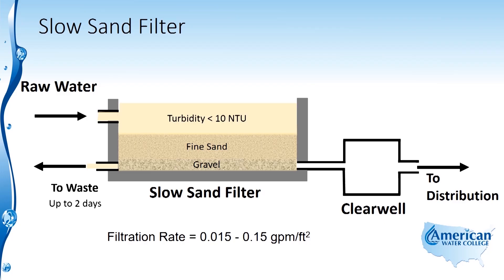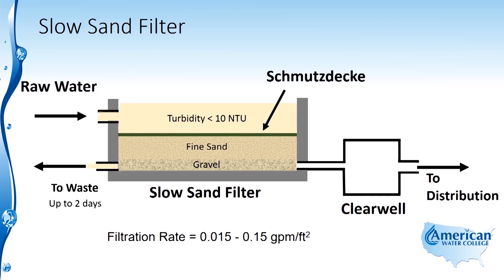It takes about two days to establish the schmutzdecke on the surface of the slow sand filter. So for the first couple of days, all that water is just going to go to waste — we're not going to use that and serve it to the public.